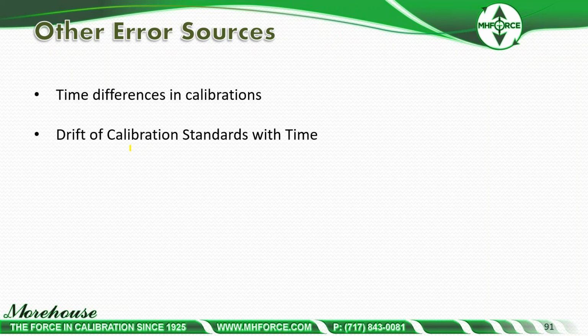Now, our competitors, or those using hydraulic frames, a lot of them do not hit the force points exactly. So the problem with the system, not really a bad one, is they interpolate the points. So at 10,000 pounds, they may apply 9,999. They may hold it, that hold may vary, and they're just manipulating all of your data. You can say, so what? It's only a pound, but they're applying interpolation curves.